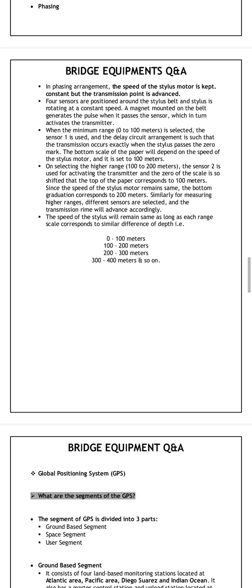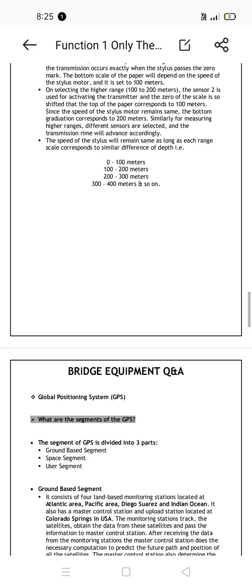Four sensors are positioned around the stylus. The stylus rotates, and it carries a magnet mounted on the belt which generates a pulse when it passes a sensor. When the minimum range of 100 is selected, the transmitter is activated exactly when the stylus passes zero. The bottom scale of the paper will depend on the speed of the stylus and is set to 100 meters. On selecting a higher range like 100 to 200 meters, sensor 2 is used to activate the transmitter, and the zero of the scale is shifted so that the top of the paper corresponds to 100 meters. Since the speed of the stylus motor remains the same, the bottom graduation corresponds to 200 meters.